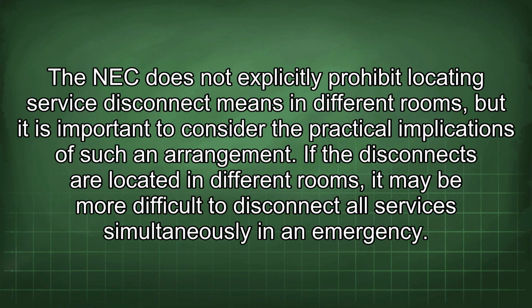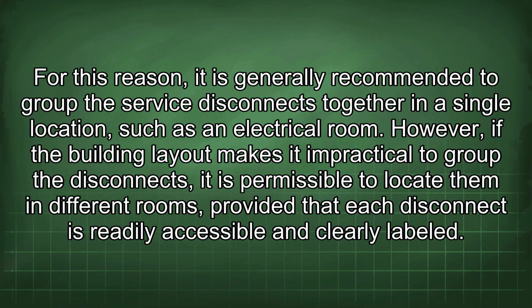The NEC does not explicitly prohibit locating service disconnect means in different rooms, but it is important to consider the practical implications of such an arrangement. If the disconnects are located in different rooms, it may be more difficult to disconnect all services simultaneously in an emergency. For this reason, it is generally recommended to group the service disconnects together in a single location, such as an electrical room. However, if the building layout makes it impractical to group the disconnects, it is permissible to locate them in different rooms, provided that each disconnect is readily accessible and clearly labeled.